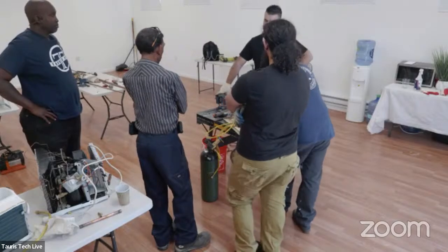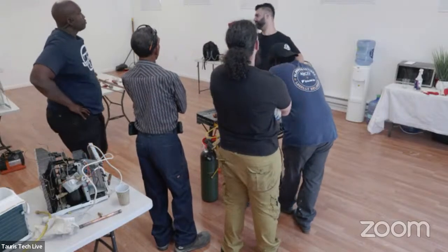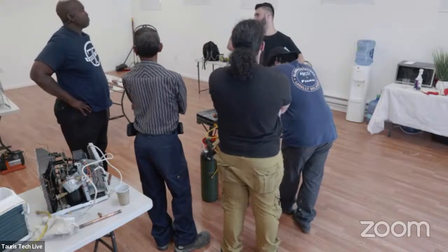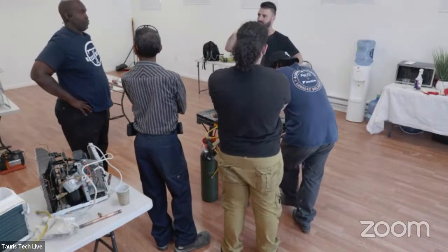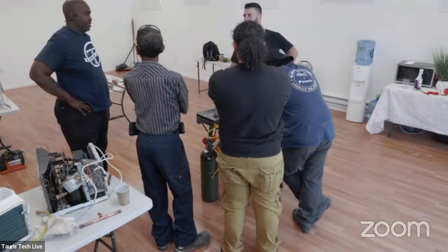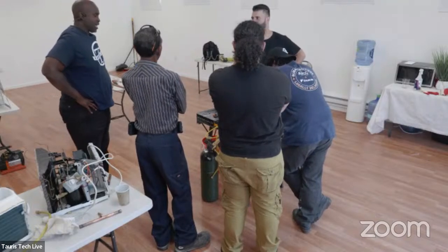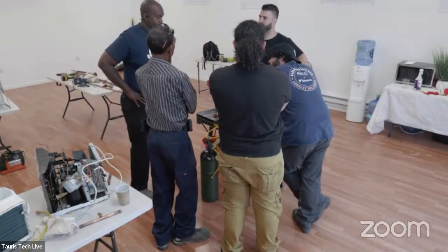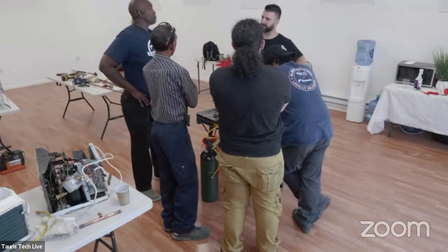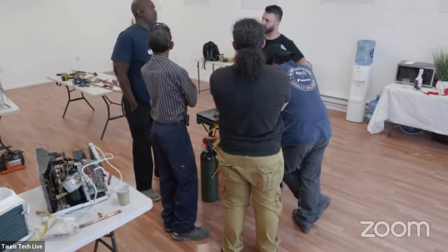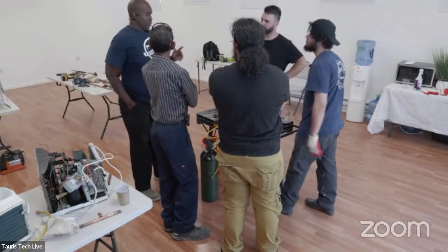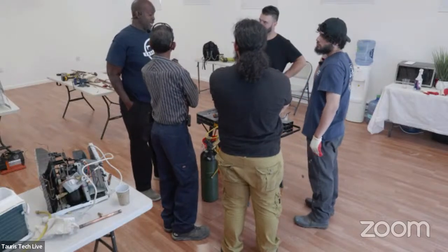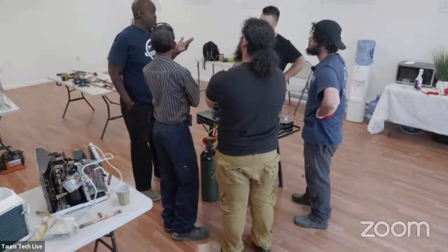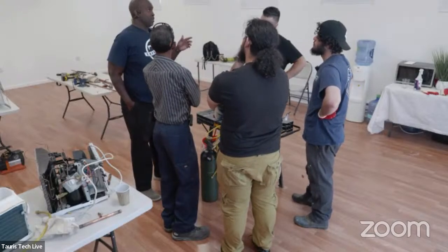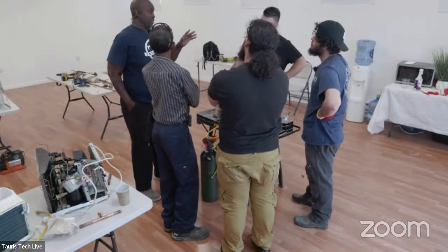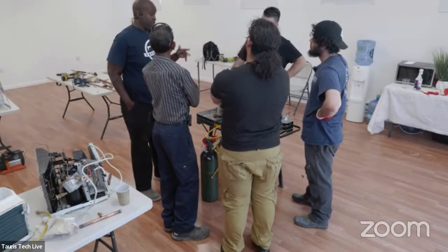And what's the normal drop, let's say, depending on the system? It's all based on the size of the system. The hose could have a little leak too, right? There's a couple of different things. So you want to put the nitrogen in there and let it settle. Sometimes you could let it settle for a whole day. And then depending upon how much the temperature drops, if the temperature drops, the pressure will go down. If the temperature goes up, pressure could go up.